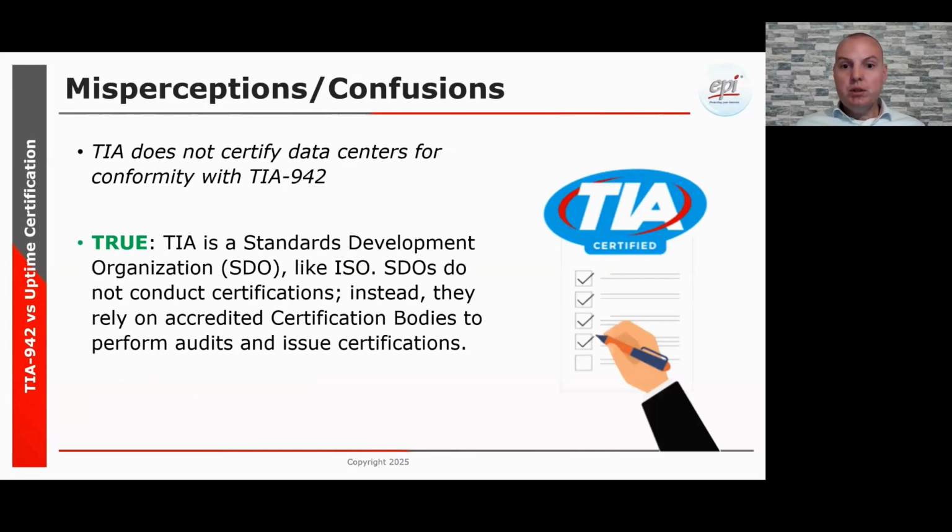The myth: TIA does not certify data centers for conformity with the TIA-942. This is true because the TIA is an SDO, the Standard Development Organization. Like ISO, SDOs do not conduct certifications by themselves. This would be a violation. Instead, they rely on accredited certification bodies like EPI to perform these audits and issue certifications.